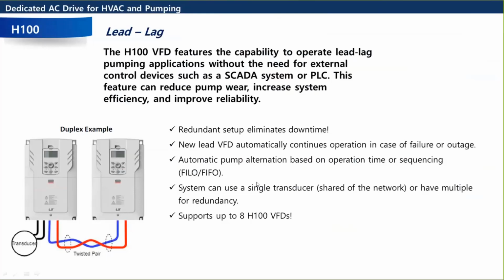You could have them use a single transducer, so all 8 drives on 1 transducer. Or you could have multiple transducers. So if one transducer goes down, it looks at the next transducer. Okay. So this is the higher level load sharing. Okay, you're going to buy more drives. It's a lot more versatile, a lot more features there.